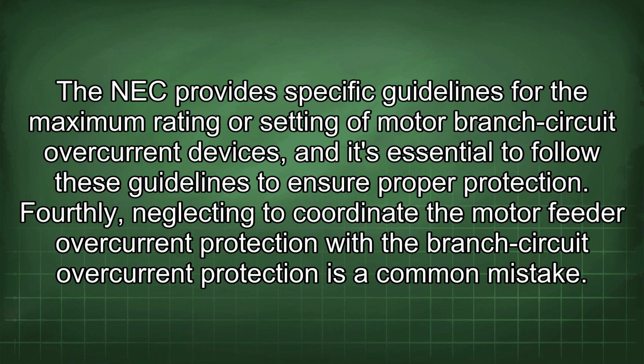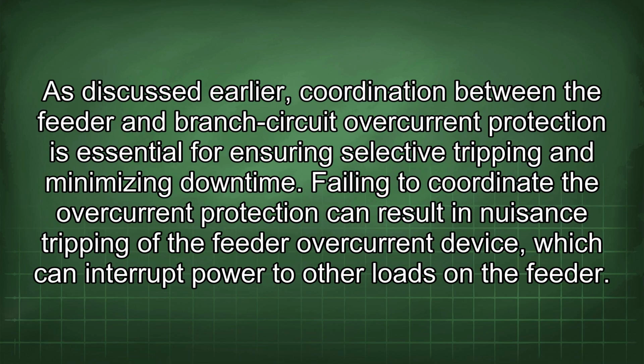Fourthly, neglecting to coordinate the motor feeder overcurrent protection with the branch circuit overcurrent protection is a common mistake. As discussed earlier, coordination between the feeder and branch circuit overcurrent protection is essential for ensuring selective tripping and minimizing downtime. Failing to coordinate the overcurrent protection can result in nuisance tripping of the feeder overcurrent device, which can interrupt power to other loads on the feeder.